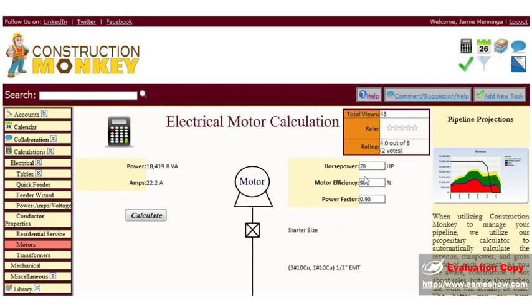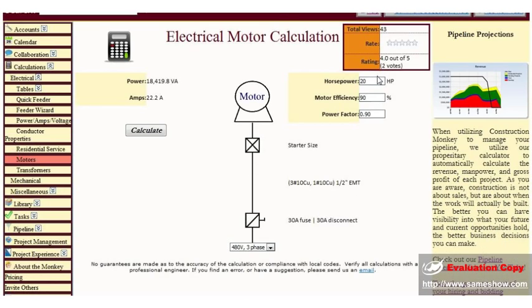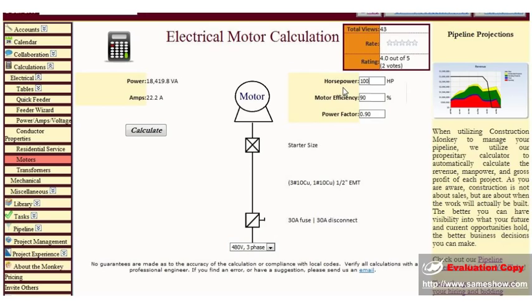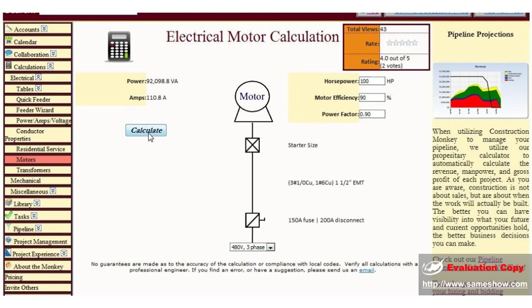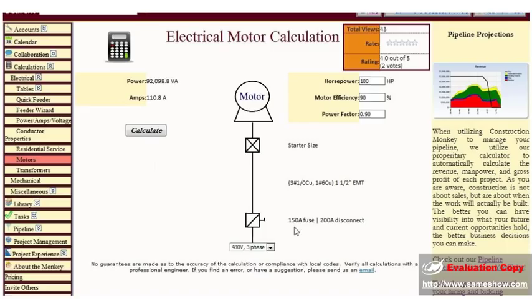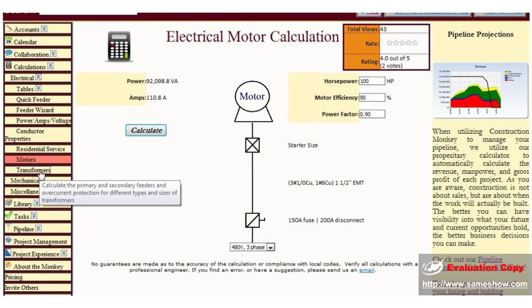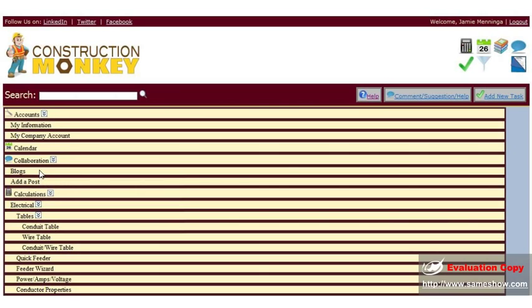We also provide a motor calculation. Just type in your information, your horsepower, your motor efficiency, your power factor. Click the calculate button. And it will give you your size of feeder for that motor, size of fuse, and size of disconnect.